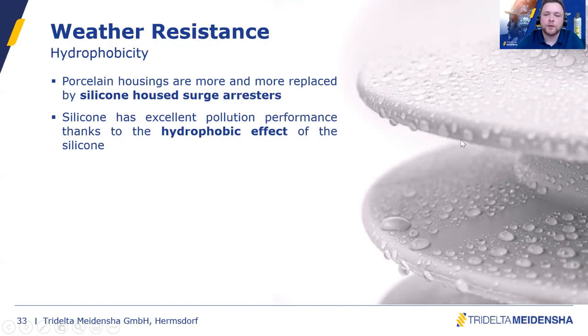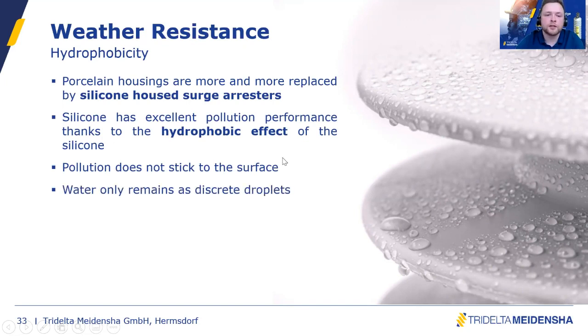But now we're talking about pollution behavior, because the silicone has a hydrophobic effect. Like you see on the right side, the pollution does not stick on the surface. The water remains as discrete droplets, like you see here, and not as one complete humid layer. It's only discrete droplets. And the arrestor cleans itself during rain. You see here this one droplet going down the shed and cleaning the surface. So this is the magic of the properly molded silicone housed surge arrestor.